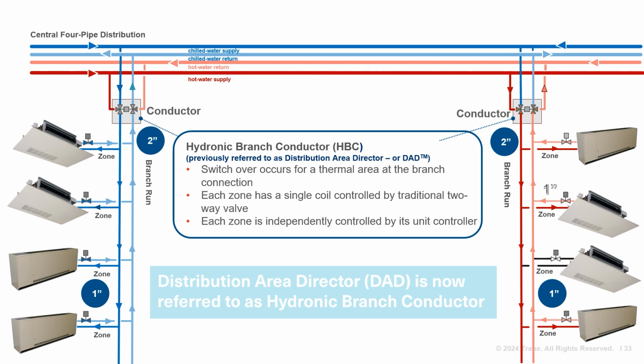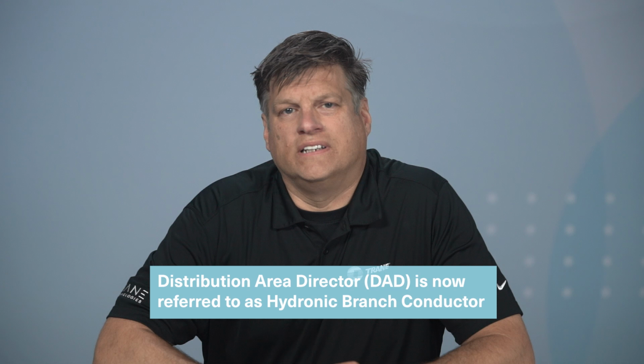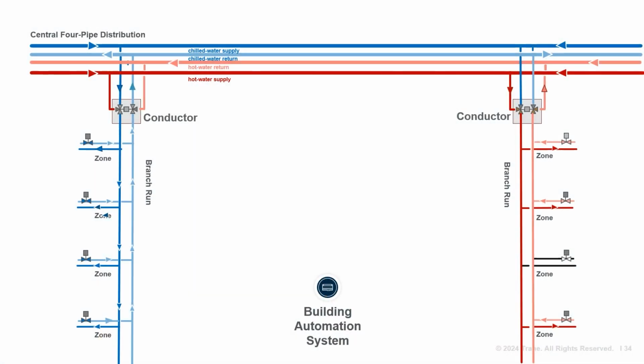Each zone still has independent control. As shown in this example, the thermal areas can be in different modes. The left-hand area is in cooling mode, so the DAD directs chilled water to the coils in these zones, while the right-hand area is in the heating mode, so the DAD directs hot water to these zones. So this approach is able to provide simultaneous heating and cooling in different areas of the building if needed. Each fan coil unit communicates its current mode to the building automation system. The BAS then determines if heating or cooling is required for that area and instructs the DAD to redirect the appropriate fluid. Let's revisit our example school.